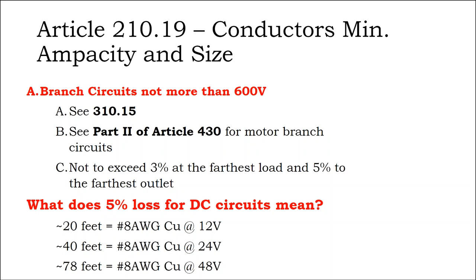So as we get further into the discussion, we'll find other reasons to derate the ampacity of a conductor, such as if you have a bunch of cables bundled together in a confined space, such as inside of a conduit, the heat from multiple cables can impact their neighbors. And so when you're bundling a bunch of cable together in conduit, there are additional temperature derate factors to consider. When you are going up on a rooftop versus inside a building, there are additional temperature derate factors to consider.